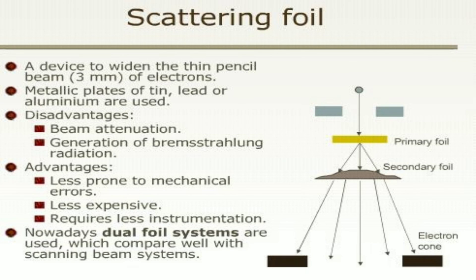A scattering foil is used to widen the thin pencil beam of electrons. Metallic plates of tin, lead, and aluminum are used. Disadvantages include beam attenuation and generation of bremsstrahlung radiation. Advantages include being less prone to mechanical errors, less expensive, and requiring less instrumentation. Nowadays, dual-foil systems are used which compare well with scanning beams.